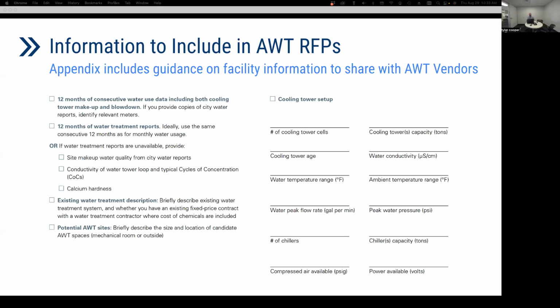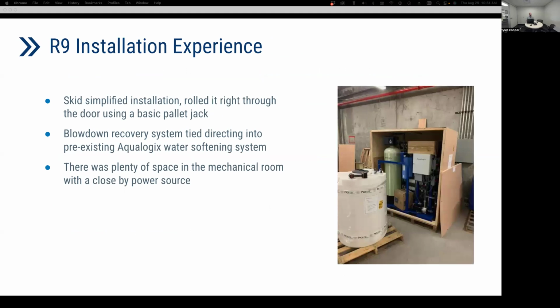And then the last piece I wanted to focus on here is from our alternative water treatment appendix. This is a sample of parameters that you'd be looking for when you're going out for solicitation for the alternative water treatment: looking at age, number of cooling towers, what capacity they're rated for, as well as the water quality parameters and operating parameters for that and the chillers. This really gives the water treatment vendors a picture of what type of technologies they need, how they need to size it, and how it would be applicable for the sites. With that, I'll pass it over to Jacob.